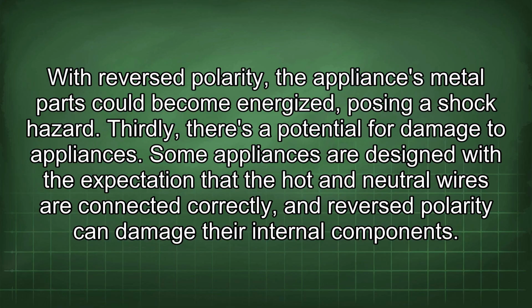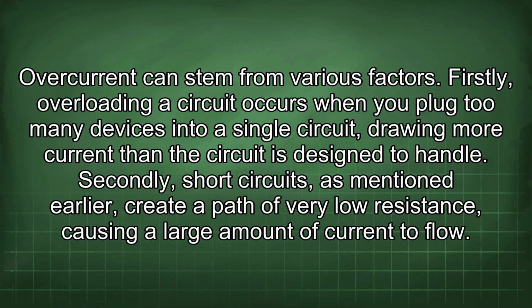Thirdly, there's a potential for damage to appliances. Some appliances are designed with the expectation that the hot and neutral wires are connected correctly, and reverse polarity can damage their internal components. Overcurrent can stem from various factors. Firstly, overloading a circuit occurs when you plug too many devices into a single circuit, drawing more current than the circuit is designed to handle.